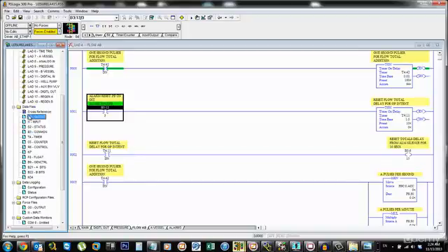I'm looking over into the data files again, and you see I have O0, I1, S2. The numbers correspond to the actual file, but the letters give us an idea of what the type is. So when we see B22 and B21 and B9, those are all bits. And bits are what the program uses to store Boolean information.